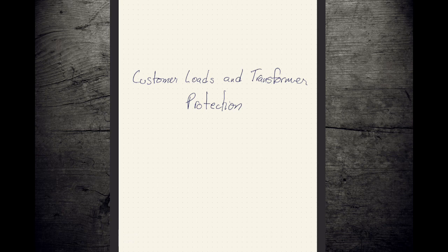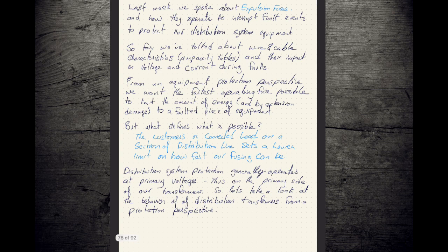Welcome, everyone. Today we're going to talk about customer loads and transformer protection. So last week we started talking about expulsion fuses, how they operate, how they interact with faults, what they do for us in our distribution system. And we talked a little bit about the wire we use and the cable and the characteristics of that and how they are imperfect and have impedance. And then under fault conditions, that's a darn fine thing because that impedance on those cables is the only thing limiting the current flow from our sources.